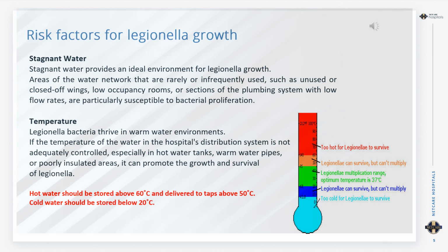The second one is temperature. Legionella bacteria thrive in warm water environments. If the temperature of the water in the hospital distribution system is not adequately controlled, especially in hot water tanks, in warm water pipes, or poorly insulated areas, it can promote the growth and survival of Legionella.